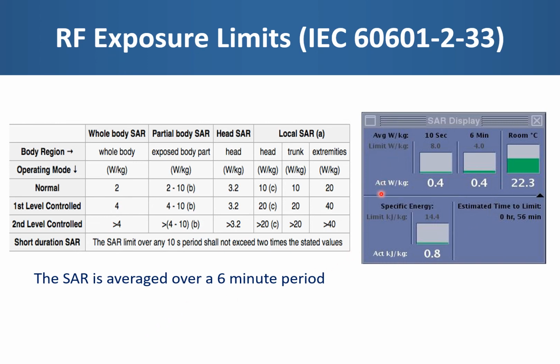The manufacturers will also provide some form of SAR monitoring, and in this case here we can see both the 10-second short duration SAR being monitored, as well as the SAR mentioned here, which is averaged over a 6-minute period. So in this case the scanner is in the first level controlled mode, so the whole body SAR peak there is 4 watts per kilogram over any 6-minute period. We also look at the MR magnet room temperature as well, because obviously if that temperature increases, then it becomes so much more difficult for the patients to actually lose the heat that they absorb from the RF pulses.